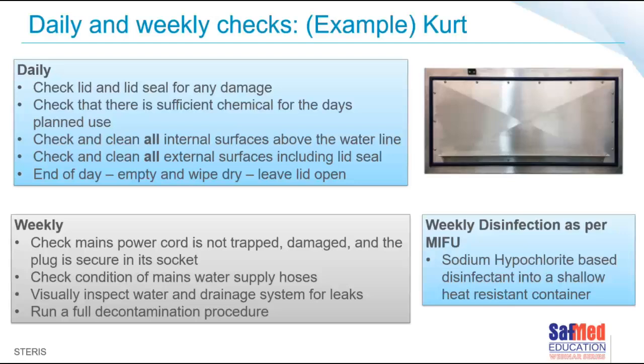Moving on to weekly checks, follow the manufacturer's instructions for use for weekly checks. As I mentioned, this is an example which I'm discussing. So once a week, do a detailed inspection. Make sure the power cord isn't trapped or damaged, and make sure it fits securely in the socket. Sometimes, because we clean the worktop where the ultrasonic is sitting, we move it, we push it back and we pinch the power cord. That's very dangerous. There's water close by and it's a cracked cord. So always make sure you check that, and then check that the water supply hoses are also not pinched, there's no wear and tear on them, and they're not cracked for any leaks.